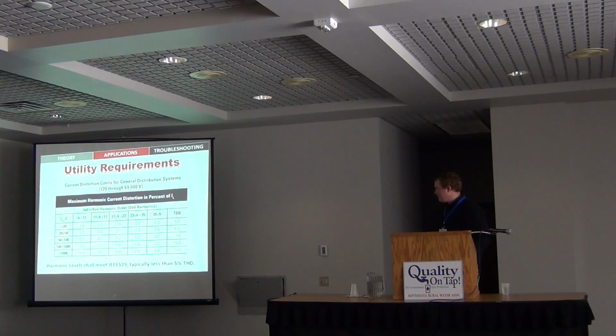So be aware that with this IEEE 519, a lot of times utilities may not enforce it, but that doesn't mean that you don't need to meet it. And I have been in situations where they do enforce it and they ask to see the design, and if we don't meet that standard, they will not let us turn on a new lift station or pump station. So if someone says, hey, you've got a panel, I'm going to put some VFDs in there and they're this much and it's going to be great, just be aware of these harmonic issues.